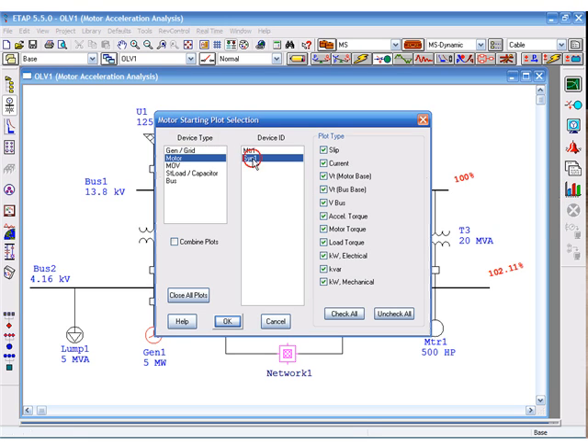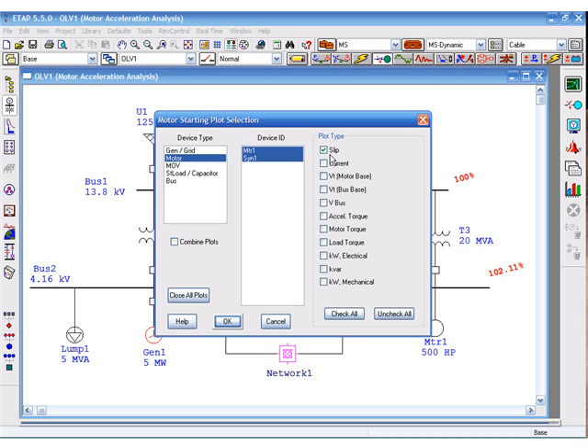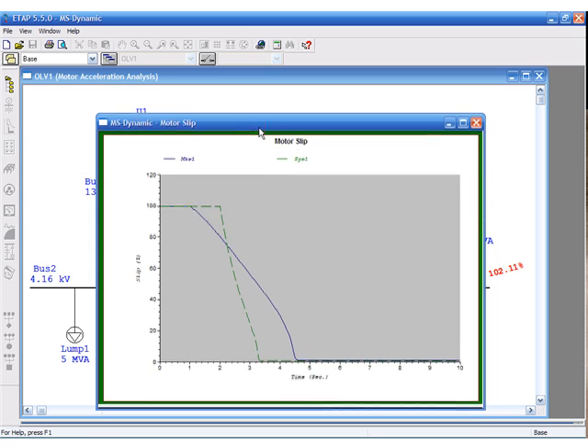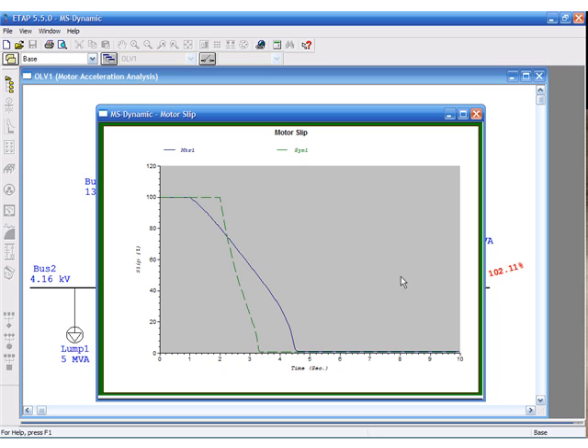Now, we have two motors that you can select simultaneously and see the slip for both motors on the same plot. Synchronous motor starts at 2 seconds and accelerates fairly quickly. Motor 1 starts at 1 second and takes about 3 and a half seconds to accelerate.